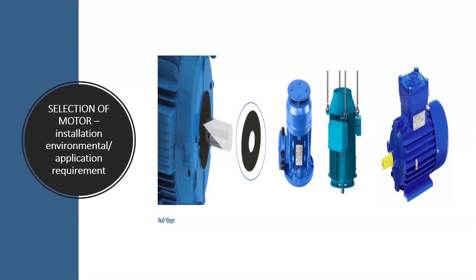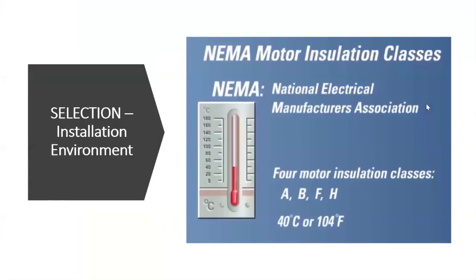So you look at your environmental factors and you choose your right application, whether you need a lot of eye bolts around the motor so that it can be mounted correctly. The general purpose motors do not have eye bolts to all the sides for the vertically mounting. So in such application, you need the right motor so that you are not faced with any challenge in the course of the installation. Also in the environment, the same environmental factors during motor installation.